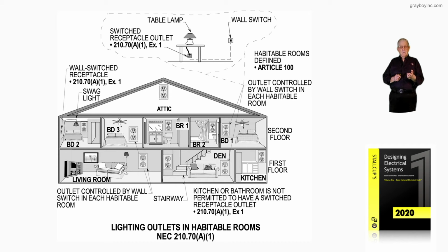And the way I read the code, the answer would be no. But if you broke the tab between the duplex and switched the top and left the bottom still energized at all times, in my opinion, then that would be legal. But this is an area where you should be sure you check with the authority having jurisdiction or know exactly what they're going to require.